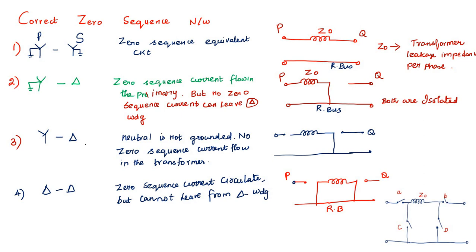For case three, Y-delta with neutral not grounded: A is open, so no zero sequence current flows in the transformer. A is open, C is open, B is open, and D is closed. For case four, delta-delta: zero sequence current circulates but cannot leave from the delta winding. A is open, B is open, C is closed, and D is closed.